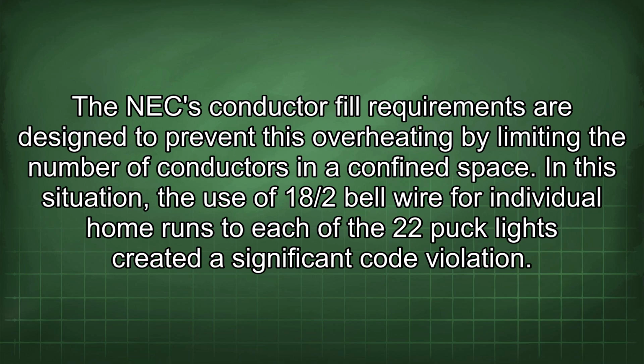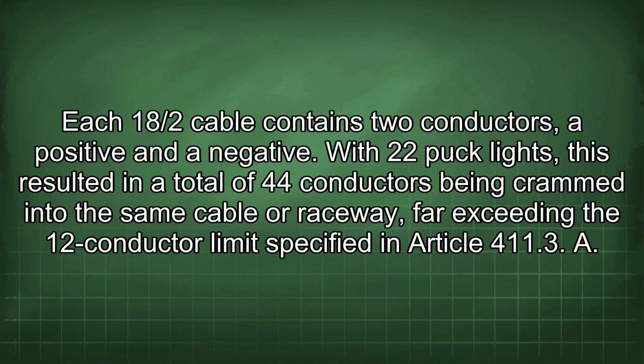a confined space. In this situation, the use of 18/2 bell wire for individual home runs to each of the 22 puck lights created a significant code violation. Each 18/2 cable contains 2 conductors, a positive and a negative. With 22 puck lights, this resulted in a total of 44 conductors being crammed into the same cable or raceway, far exceeding the 12 conductor limit specified in Article 411.3.